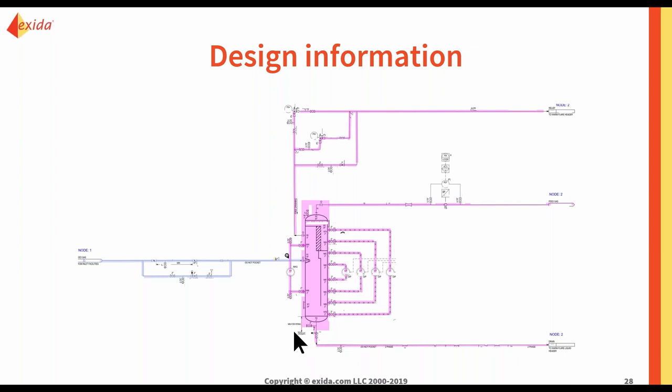So we actually introduce and make up a new hazard over there, in a way that we are going to over-design the safety system. So maybe we put more burden on this particular SIF, and the SIF being at a higher SIL level is not just about buying more expensive instrumentation, but also you have to maintain it. And there's also an overhaul problem with it. I'm going to go into details on that later in the following slides.